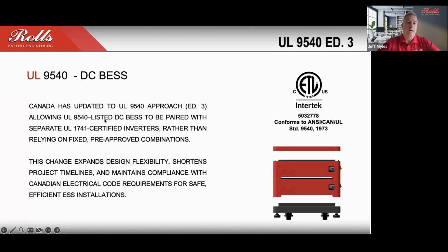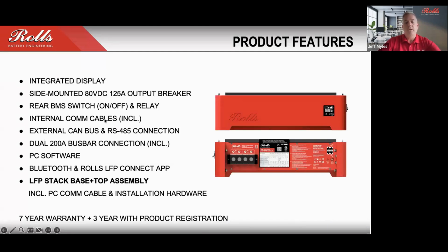And so any UL 1741 certified inverter will be compatible with these units and also will be compliant with the regulations for residential energy storage. So this particular unit, the S48100 LFP Stack LV, is a modular stackable ESS solution. The modules are each 51.2 volt, compatible with 48 volt system configuration. They're each 100 amp hour capacity, and you can stack up to 8 of these units together in one stack for essentially a 40 kilowatt hour system.